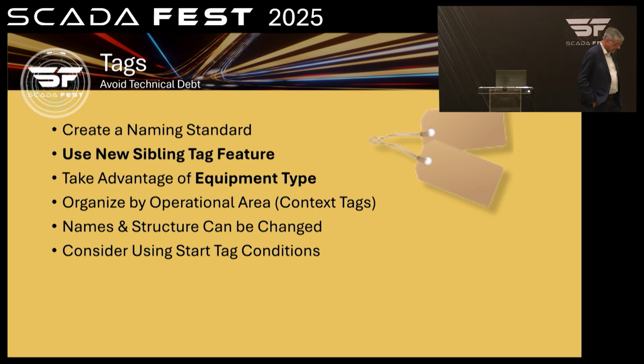There's a start tag condition on tags. This is useful if you have sub-areas of the plant or utility where you want to run a smaller subset of tags on one machine than on another. The start tag conditional can check if the workstation name is this, and if so, don't start this driver or these tags, since this context isn't useful to that machine. This allows you to use a lower capacity computer with a lower tag count. It's a useful tool, and you can set it so that on a given machine you only turn on certain groups of tags.